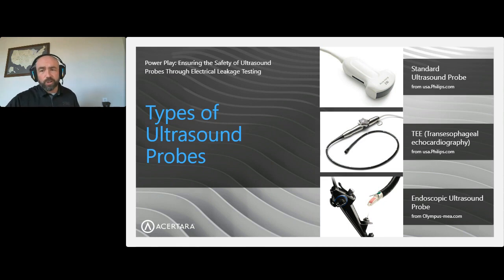That's true that you'll get a passing result if you don't require all of them. But generally speaking, that's a passing result you'll often see on older models of electric leakage testers. You're not actually testing the probe, so you're missing a critical component of that circuit to be able to actually test it. It's definitely a patient safety issue if you're not actually getting that information.